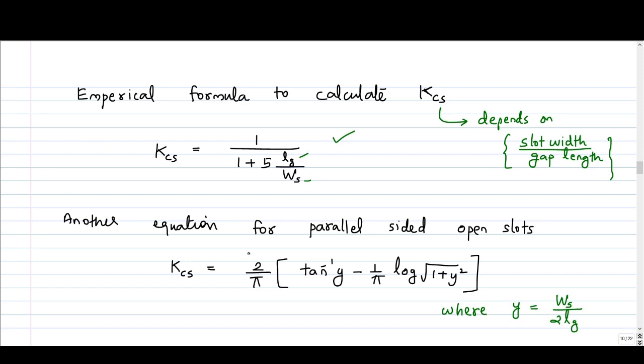Another empirical relation is available for parallel sided open slots. It is shown here. Kcs is equal to 2 by pi into tan inverse y minus 1 by pi into log of root 1 plus y square, where y is slot width divided by 2 times length of air gap. So these empirical relations are useful for doing numerical problems. Sometimes they will be directly given in the question. If not given, you should remember this expression. Kcs is equal to 1 by 1 plus 5 into lg by ws.